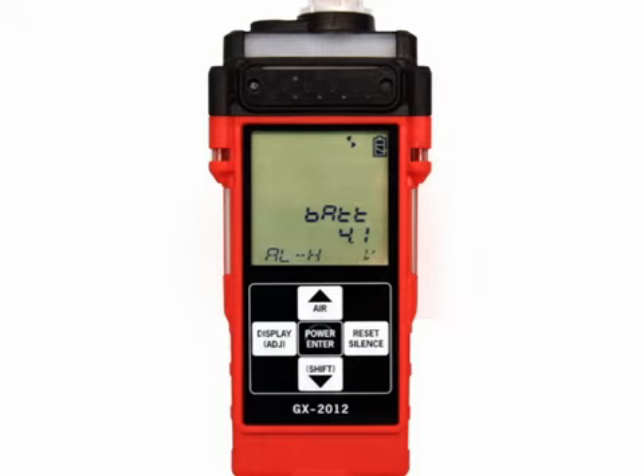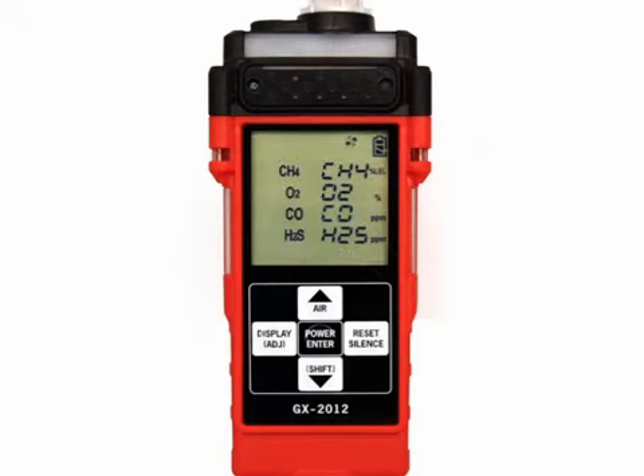ALH indicates the latching alarms. ALA indicates self-resetting alarms. The remaining screens are only displayed for about a second each. You will see the full-scale values for each channel, the low alarm point for each channel, the high alarm point for each channel, followed by the STEL and TWA set points for carbon monoxide and hydrogen sulfide.